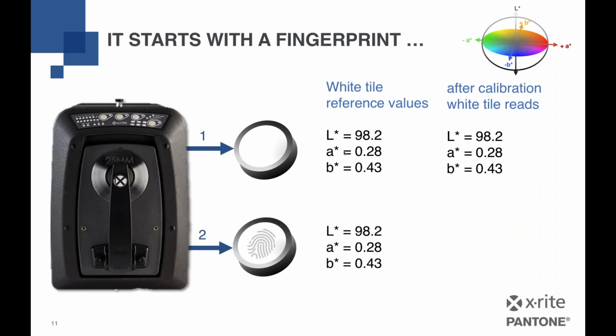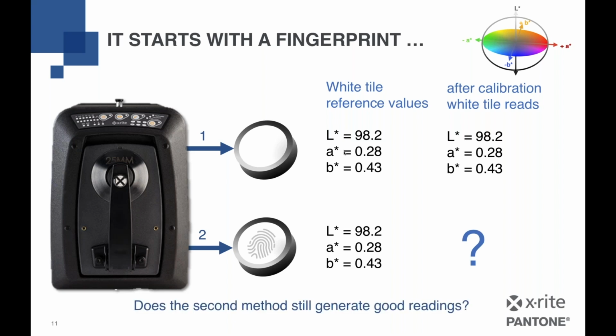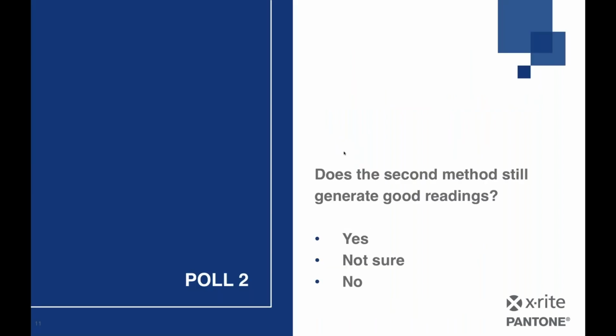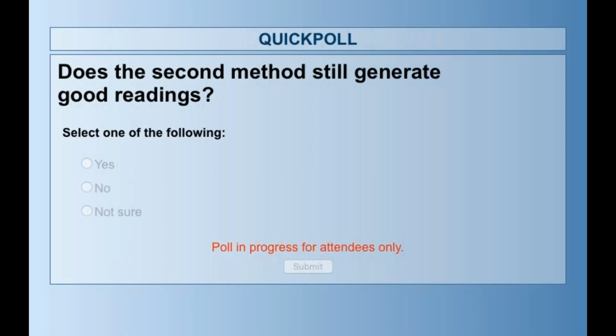Now, what if your white tile is actually contaminated or dirty, like with a fingerprint? Would it still read the same reference values, and would that still make good color readings? So that's the second poll question we want to ask you. Does that second method of calibrating your instrument with a dirty white tile still generate good readings? Give it a yes or no or a not sure, please.